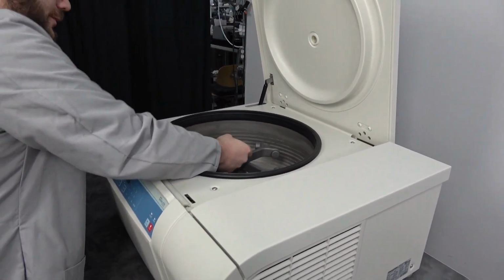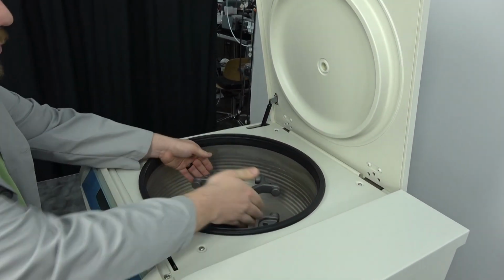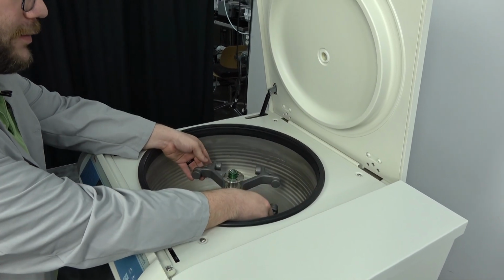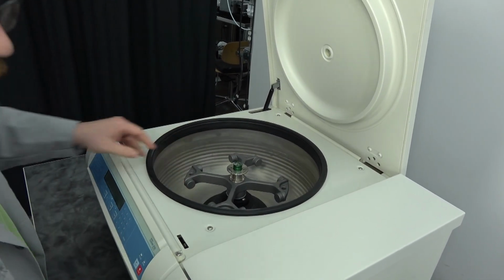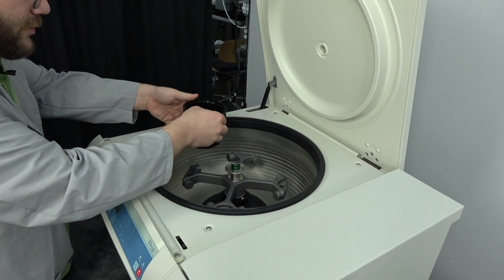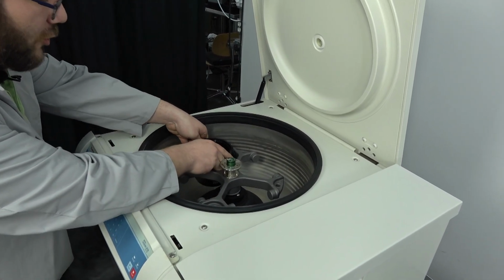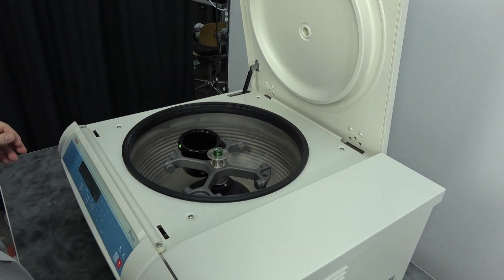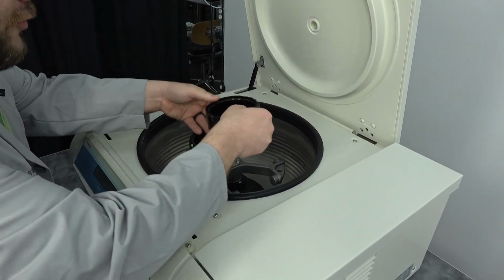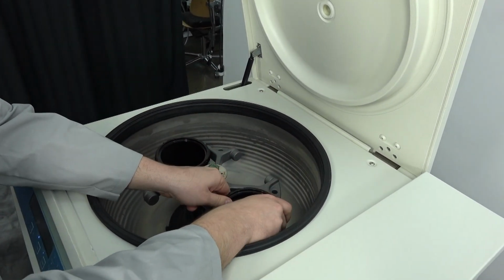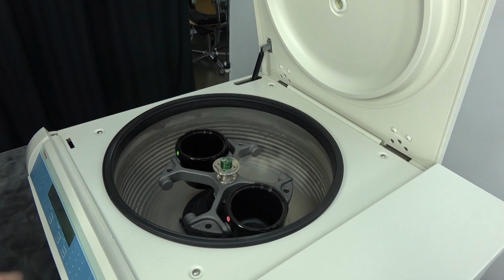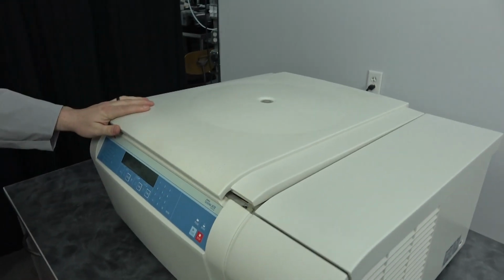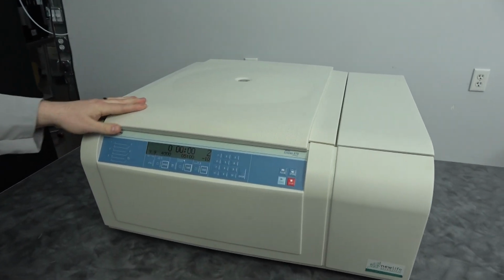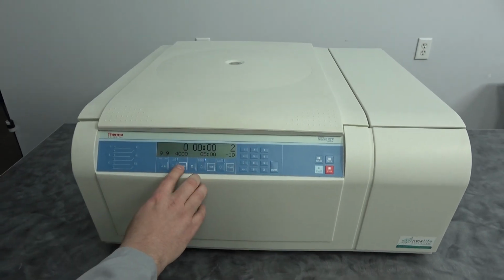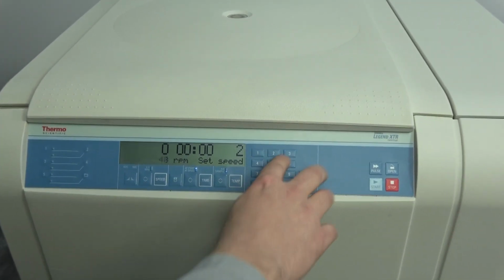So from here, you want to go ahead and load up your rotor. Make sure it's properly seated, that it's not wobbly, and that it is properly and fully seated so that it sits completely upright. Load your buckets onto your rotor in accordance with the manual specification, which should be in a balanced format. From there, you want to go ahead and shut that lid. Here on the front of the unit, you have your basic speed settings, where you can program in your settings.